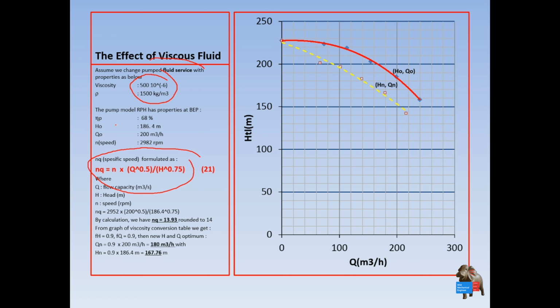Okay, and then you have efficiency, head, etc. But when you change the viscosity, then you need to change the effect on the flow and total head, and this will be the new numbers for the flow.